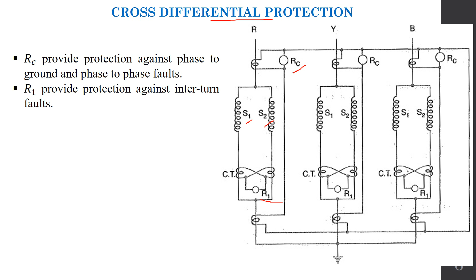During the normal operation, the current in the two halves of the stator winding S1 and S2 will be equal to each other, and therefore the CT secondaries will also be equal to each other, and no current will be flowing in the relay R1. But when an inter-turn fault occurs, suppose let us say in S1, then the current flowing in S1 and S2 will now be differing from each other, and as a result the CT secondary current will also be different from each other. Hence the difference of the current will be flowing in the relay R1, and since a current is flowing in the relay R1, this will make the relay operate, and thus the generator in this case will be disconnected from the system.